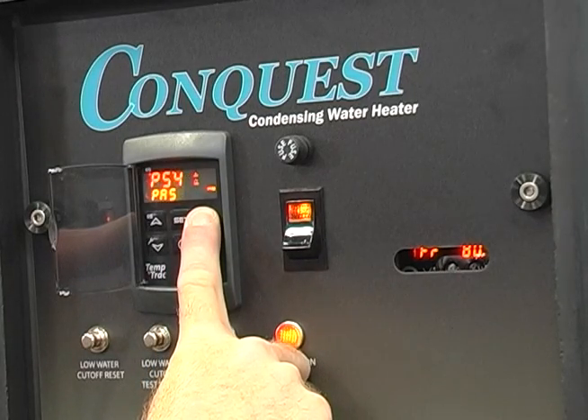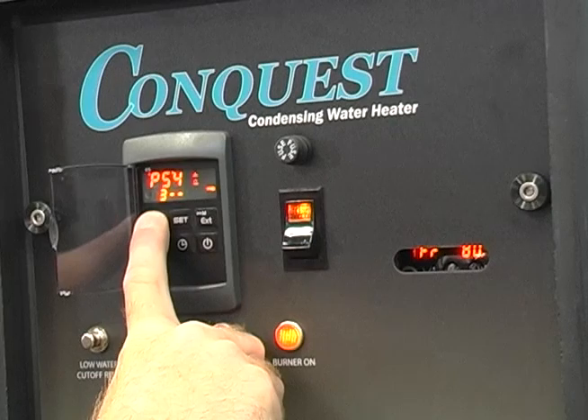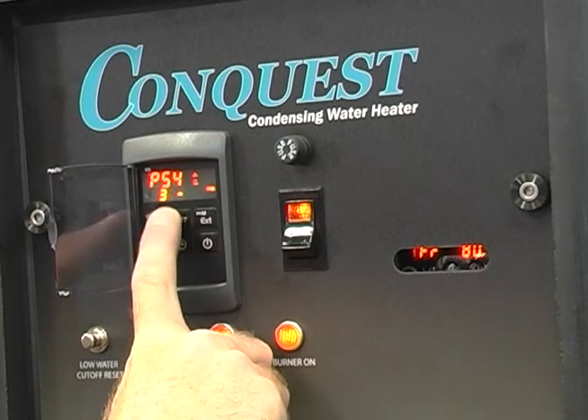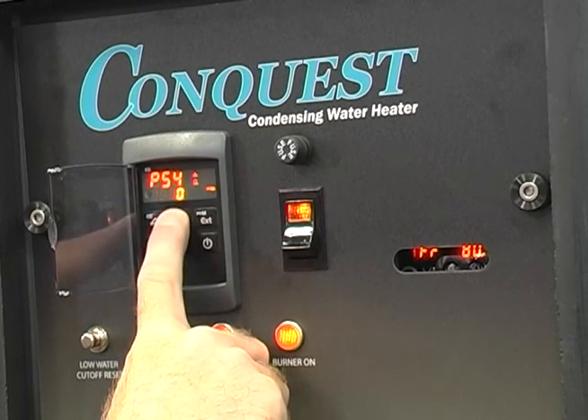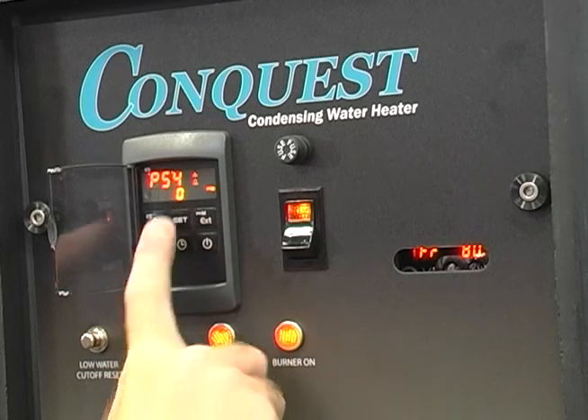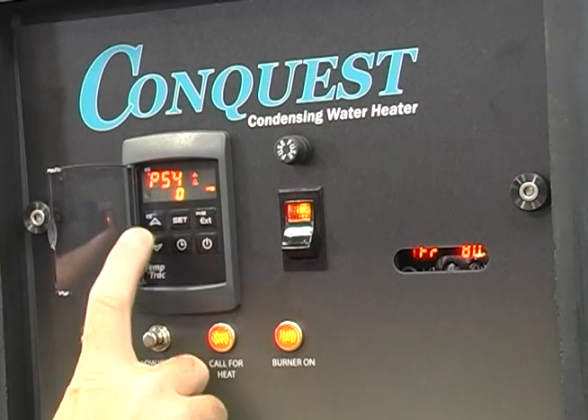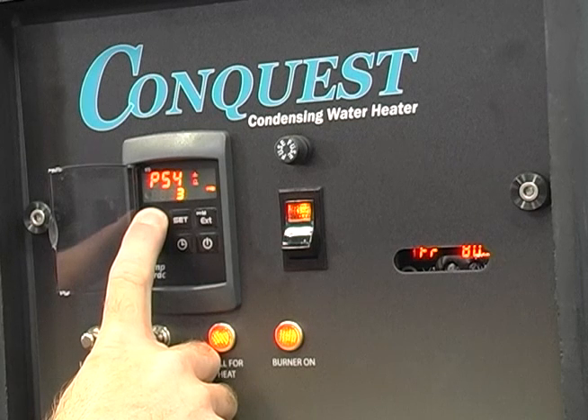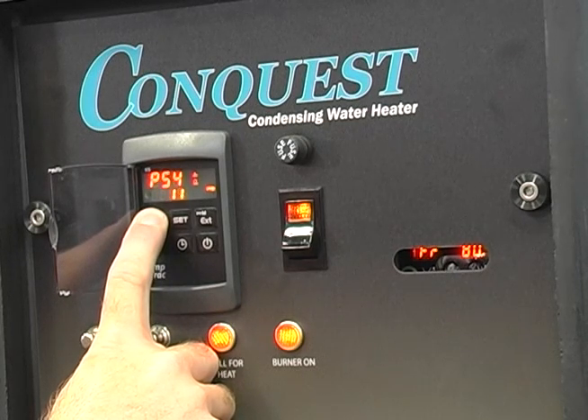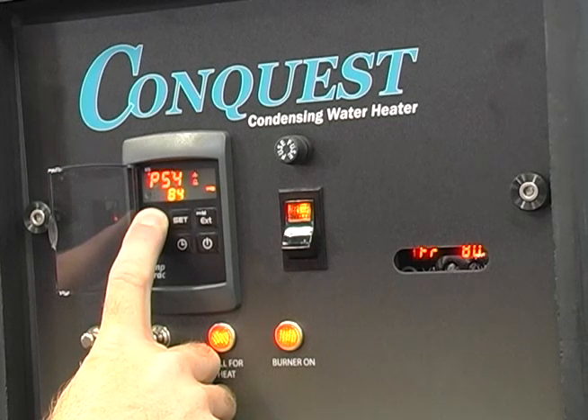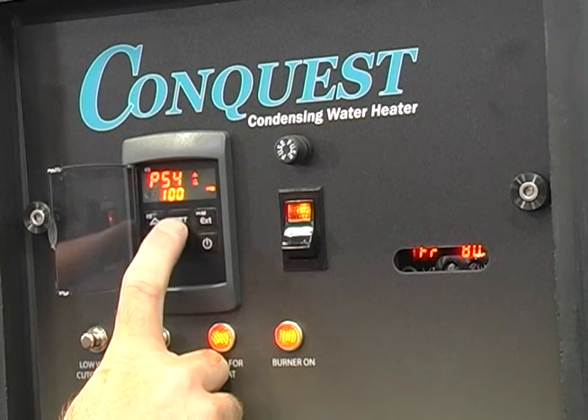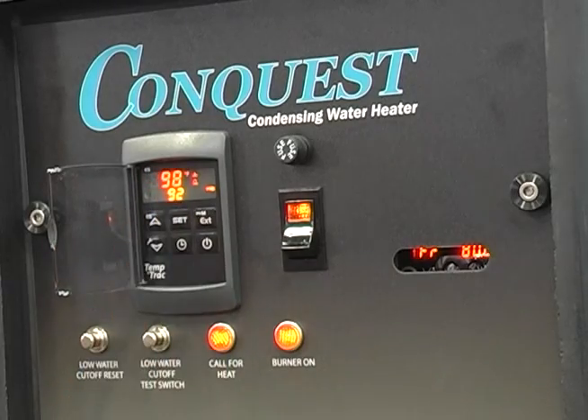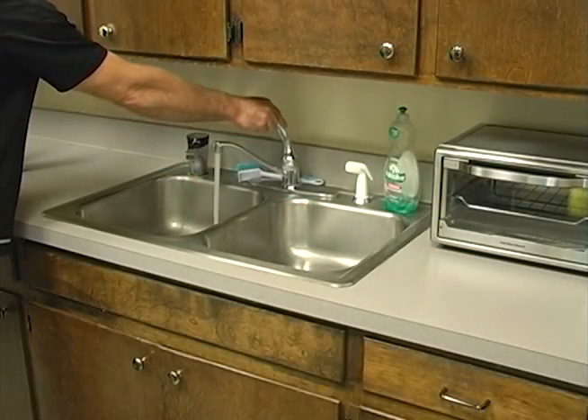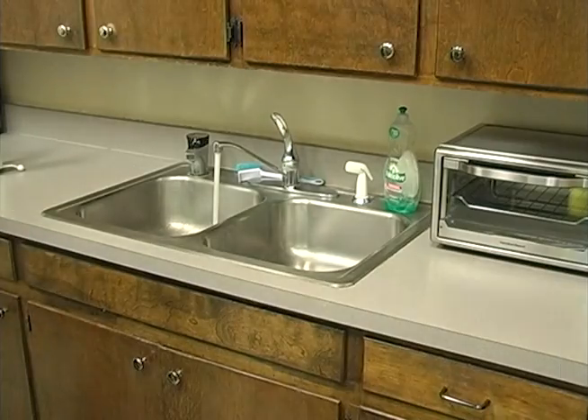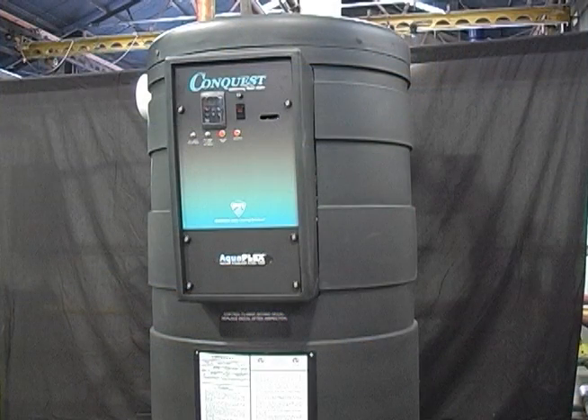Once the desired combustion is achieved at low fire, manually adjust the TempTrack control to high fire. Do this by pressing and releasing the set key. Press the up arrow key until the parameter reads 100. Once again, press the set key to lock the water heater into high fire. When adjusting combustion in high fire, it may be necessary to open a hot water outlet to provide flow through the water heater to prevent or delay the water heater from reaching operating set point and ending a burner cycle.